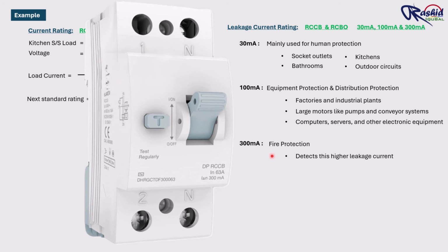That is why 300 mA RCCBs are commonly installed at the main incomer or main distribution board, while 30 mA RCCBs are installed downstream on final circuits such as sockets, bathrooms, kitchens and other outdoor circuits where people may come in direct contact with electrical equipment.